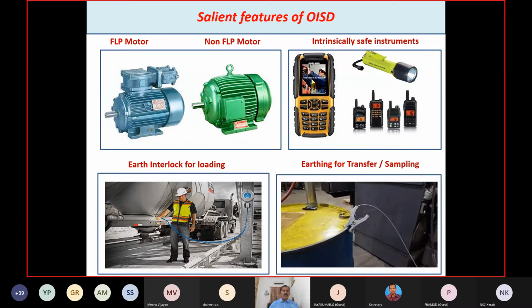Then the interlock for loading. Before loading any trucks, earthing is very important to avoid static charges. So now an earth interlock system has been adopted in all industries. If earthing is not provided, you cannot load the trucks. Even during loading, if the earth gets disconnected, the loading will be suspended. This system is also followed in all oil and gas industries.